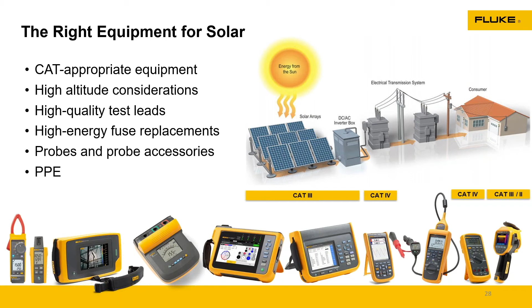Also, some of these installations are in high altitudes. So we want to take those considerations into play when we think about category rating as well. Very high altitudes will derate your meter and the capability of that. You just want to make sure that you're using the right stuff. A part of NFPA 70E states that part of your personal protective equipment is your digital multimeter. It's an extension of your protection. So you want to make sure that your test leads are good and that your meter is appropriate for that job. And make sure that you're using the right PPE.